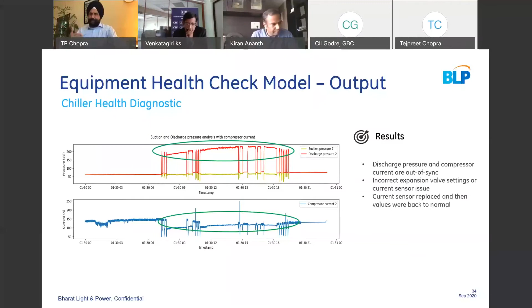So just very quickly, to capture the 3 takeaways from this project. One, we were able to get energy savings just by dynamically changing the set points for these buildings or factories based on the weather conditions and environmental conditions, and predicting what it needs to be. 2, about 7% by dynamically varying the variable frequency drive set points. And 3, close to about 10% by just changing the chiller sequencing and the chilled water valve modulation. And as a result, in this limited period of time, we were able to get 9% energy efficiencies using these algorithms going forward.